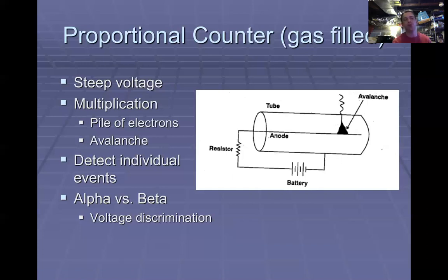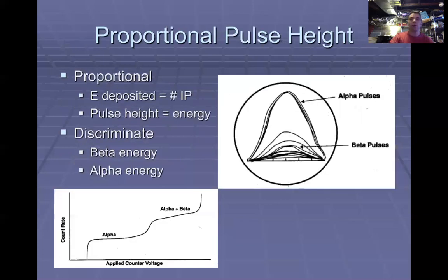So this is very useful for contamination surveys, for compliance in areas where we're doing alpha therapies and the like. Okay. Oh, I got ahead of myself. So this is how it achieves the alpha beta discrimination. And if you can set your threshold somewhere between the peak of a very energetic beta and the higher peak of an alpha, you can get a very successful discrimination.